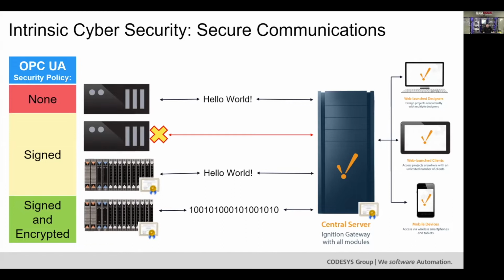With OPC UA, you can have multiple different security policies. A standard OPC UA connection doesn't require any level of security—you can set a none security policy. That means you don't have a certificate on either the controller side or the SCADA side, and there's no security for authentication or encryption, so any device can connect.